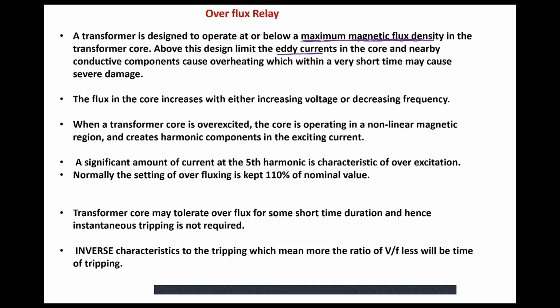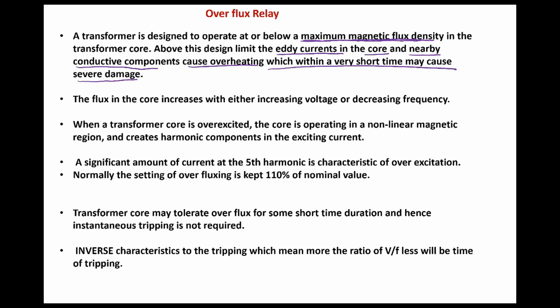The eddy currents in the core or nearby conducting devices will cause overheating and severe damage to the transformer. If you saturate the transformer core, what is the danger? The eddy currents are induced, not only in the transformer core but also in the surrounding conducting devices, which will cause overheating. In simple layman's language, the core losses of the transformer increase.